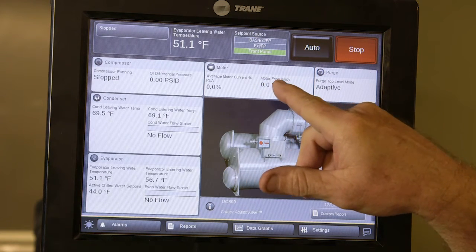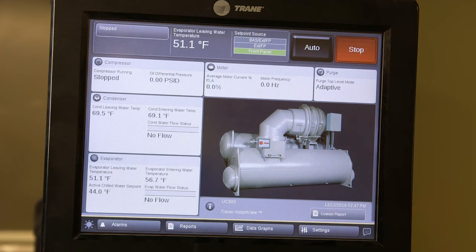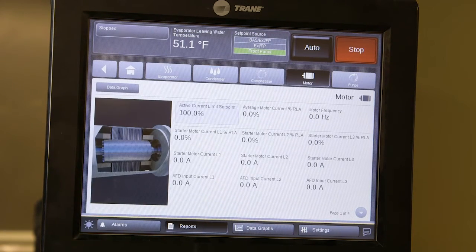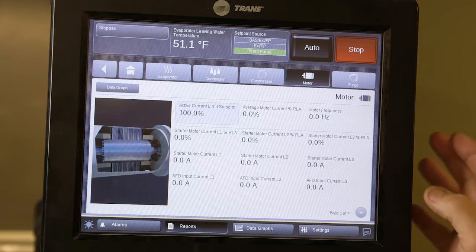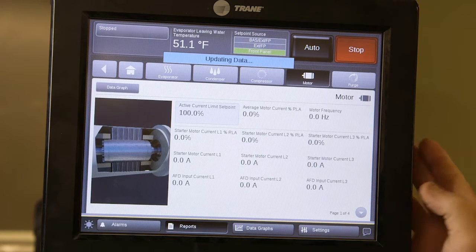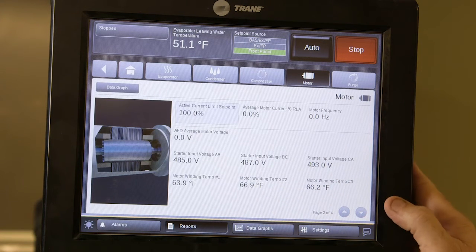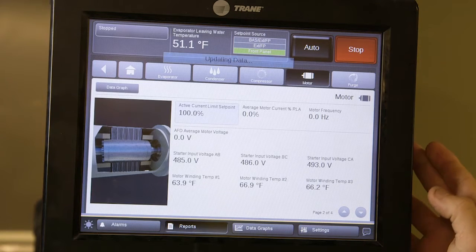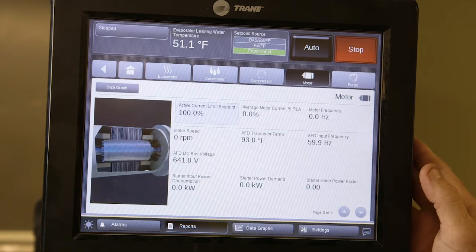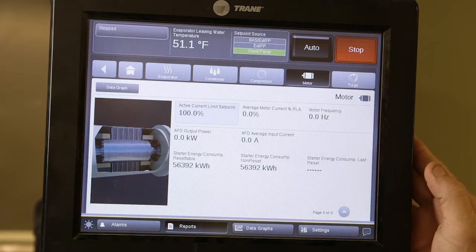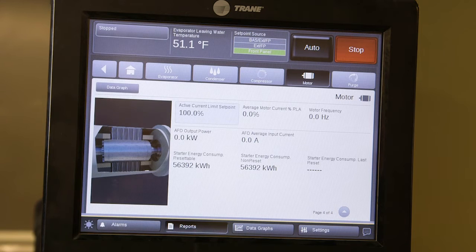From the main menu you have motor operating parameters and purge operating parameters. If you click on motor, it will open and give you four pages of information on how the motor is operating. Scrolling through, you'll see amperages, starter input, winding temperatures, the transistor for the frequency drive temperature — which is very important — and your energy consumption ratings. This is a way you can monitor the energy costs of operating this chiller.